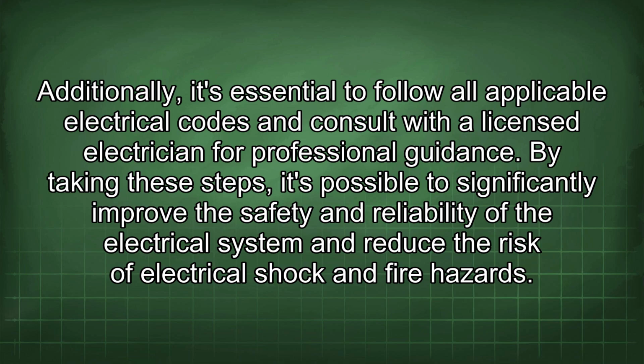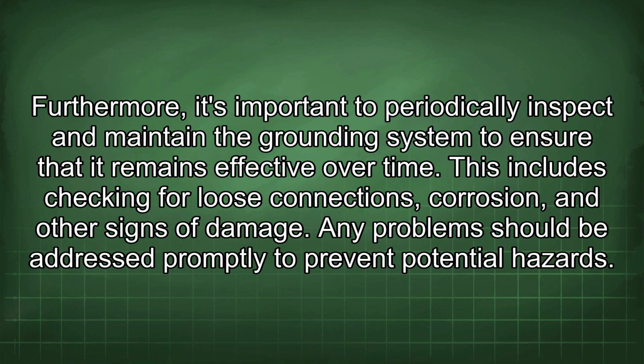By taking these steps, it's possible to significantly improve the safety and reliability of the electrical system and reduce the risk of electrical shock and fire hazards. Furthermore, it's important to periodically inspect and maintain the grounding system to ensure that it remains effective over time. This includes checking for loose connections, corrosion, and other signs of damage. Any problems should be addressed promptly to prevent potential hazards.